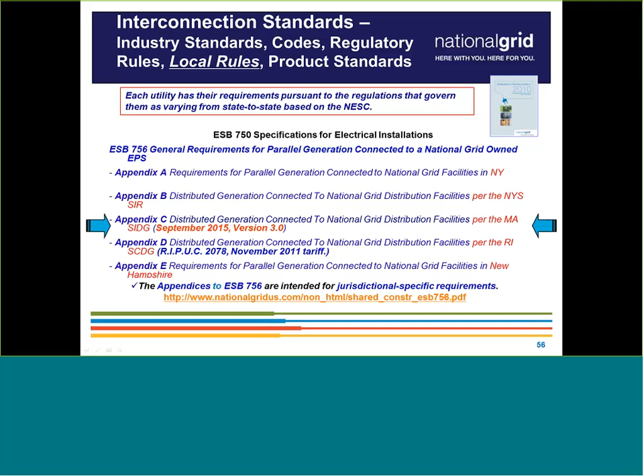In that document, we cover the manual disconnect and main overcurrent protection. That could be a pole mount load break switch for a complex large job, or something in switchgear if you're a behind-the-meter customer. It covers overcurrent protection, so you need a 51C and a 51G — those are requirements for 500 kilowatt or greater projects, among other relay elements. It also covers interface points, which can get specific depending on your application, because it really comes down to what your electrical room looks like.